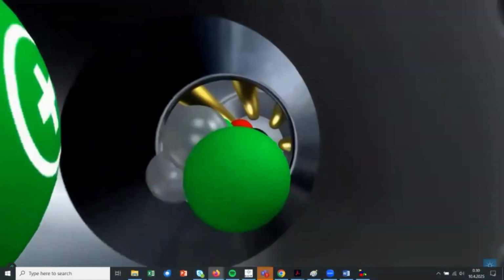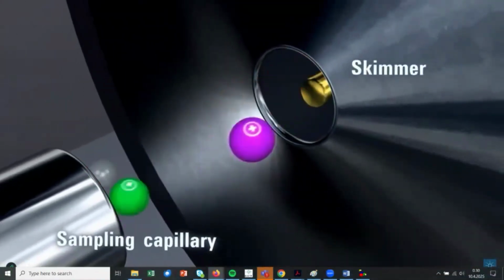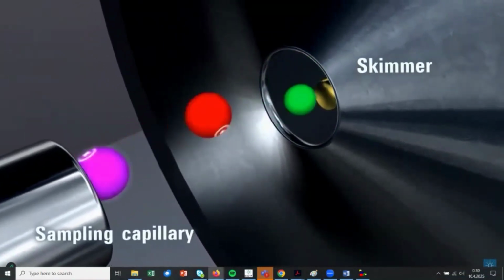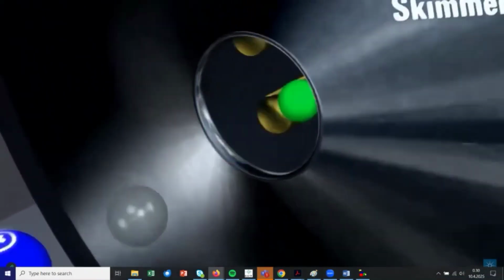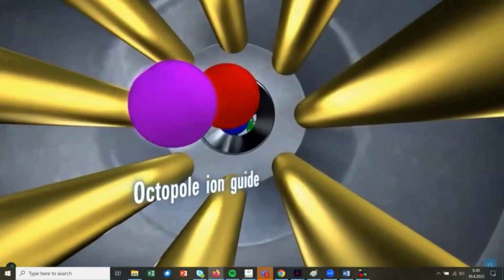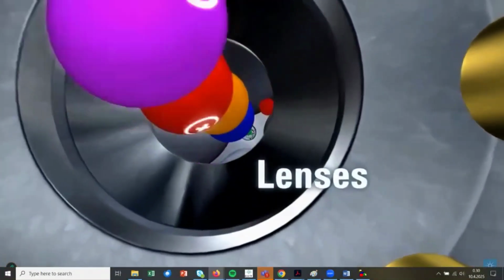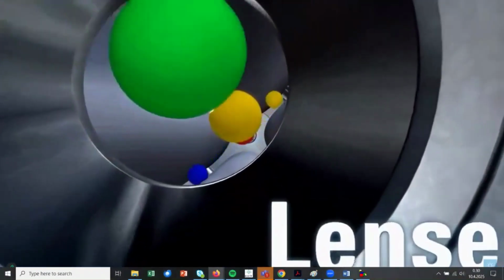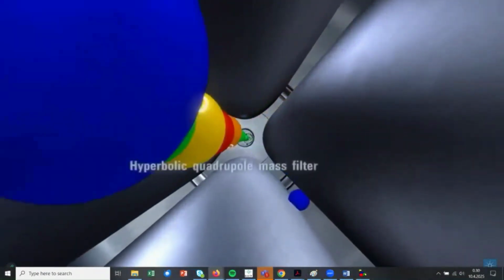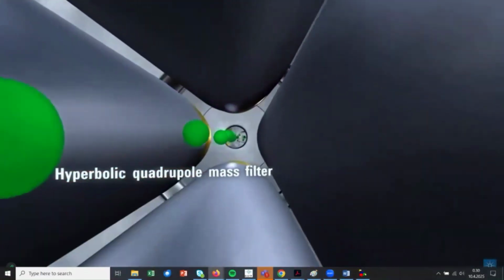We guide the ions forward. A thin skimmer aperture, carefully matched hole size, and short capillary to skimmer distance reduce beam broadening. An on-axis octopole ion guide provides nearly 100% ion transmission over a wider mass range. Patented lenses enhance high-mass ion transmission and increase sensitivity over a wider mass range. The quadrupole mass filter allows only ions of the target mass to pass through.